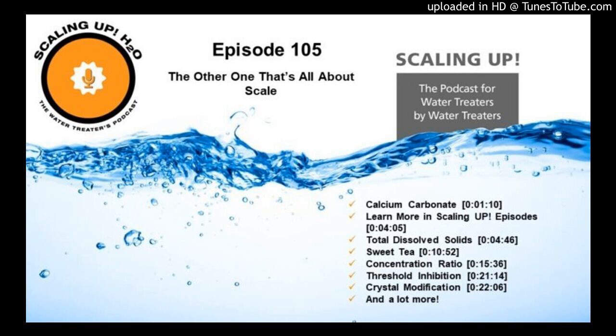Calcium carbonate is a combination of 5 things. And I'm just going to go right into an explanation of what those 5 things are. So we have alkalinity, hardness, pH, dissolved solids, and temperature. If you have listened to earlier shows, you have heard me speak on stability indices, and there's 3 of them out there. There's the Langelier, there is the Ryznar, and there is the Puckorius. I used to call it the practical, but we lost Paul Puckorius very recently, and I'm honoring Paul by calling it the Puckorius Scaling Index.